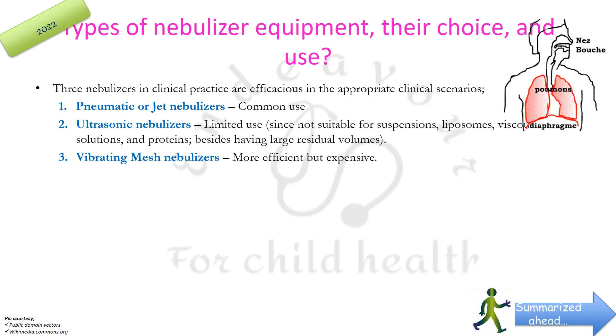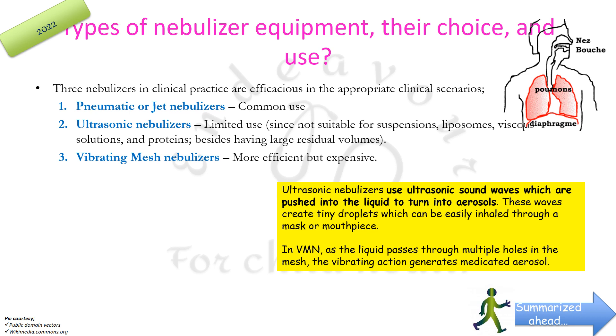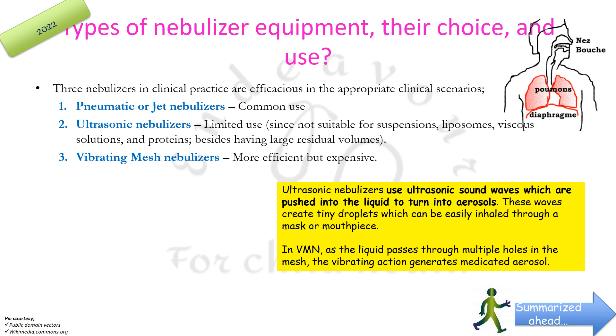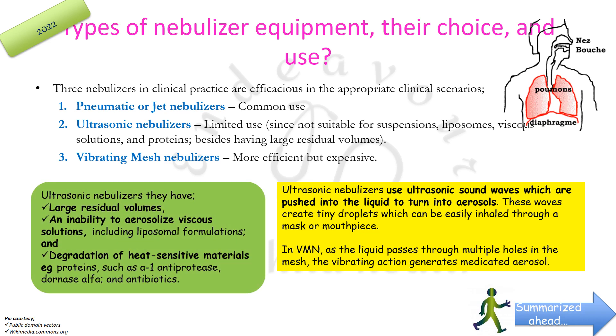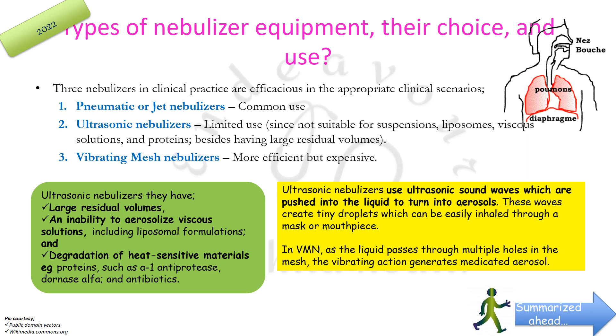Vibrating mesh nebulizers are more efficient but very expensive. Ultrasonic nebulizers use ultrasonic sound waves pushed into the liquid to generate aerosols that can be inhaled through a mask or mouthpiece. In vibrating mesh nebulizers, as the liquid passes through multiple holes in the mesh, the vibrating action generates medicated aerosols. Ultrasonic nebulizers have large residual volumes, cannot aerosolize viscous solutions including liposomal formulations, and may cause degradation of heat-sensitive materials such as alpha-1 antiprotease, dornase alfa, and antibiotics.